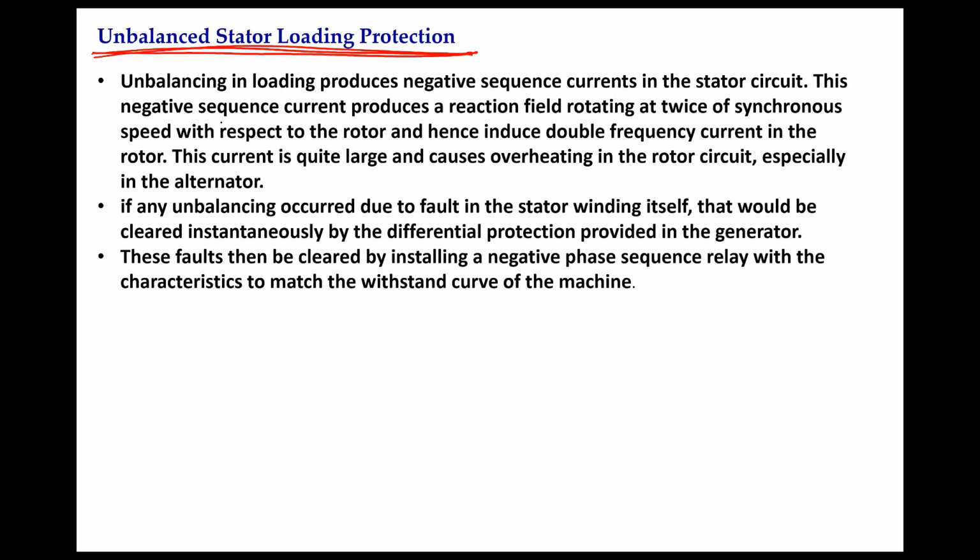These negative sequence currents produce a magnetic field that rotates at twice synchronous speed with respect to the rotor, and hence induces eddy currents of double the frequency inside the rotor. When this current is quite large, it causes overheating of the rotor.